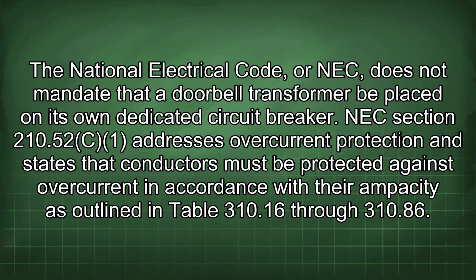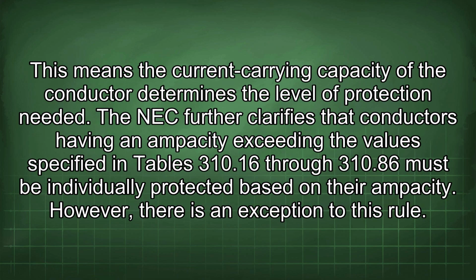The National Electrical Code, or NEC, does not mandate that a doorbell transformer be placed on its own dedicated circuit breaker. NEC Section 210.52 addresses overcurrent protection and states that conductors must be protected against overcurrent in accordance with their ampacity as outlined in Table 310.16 through 310.86. This means the current carrying capacity of the conductor determines the level of protection needed.